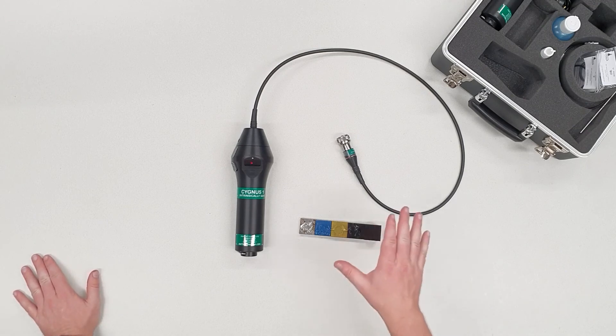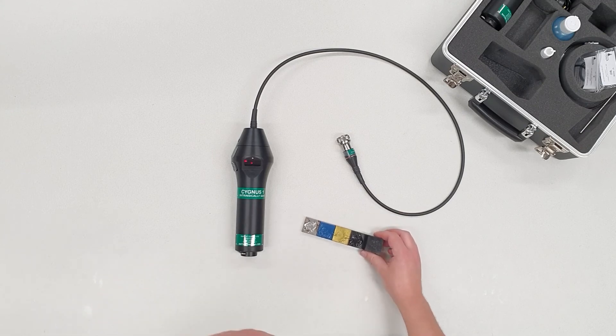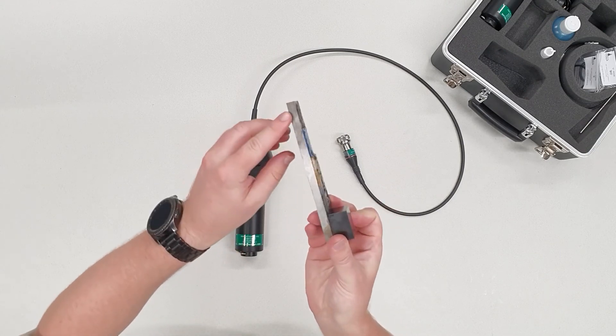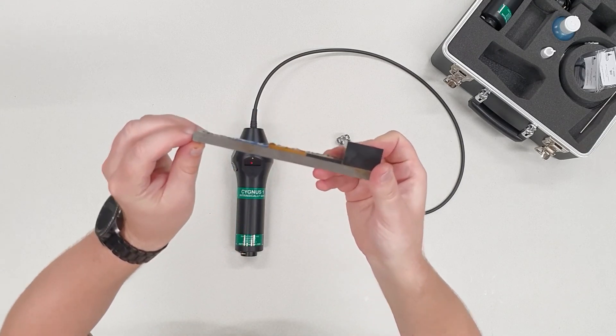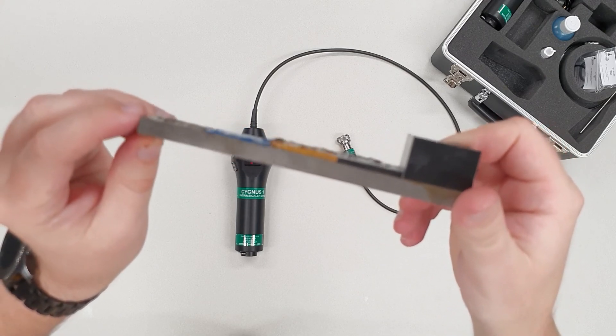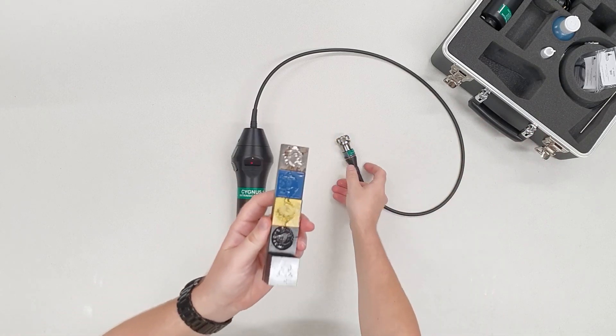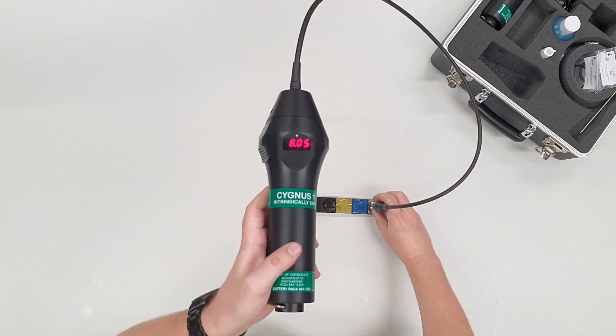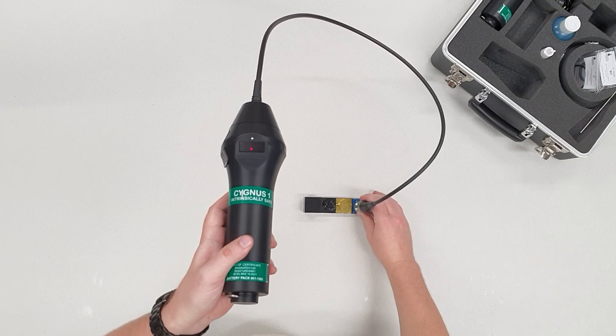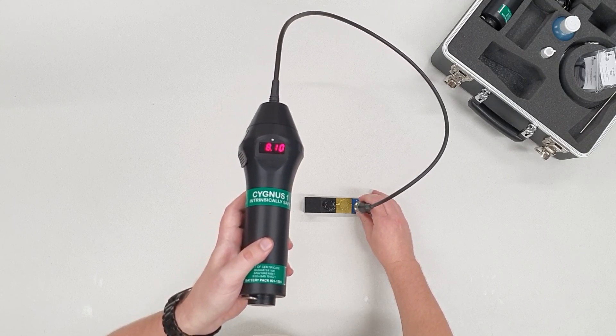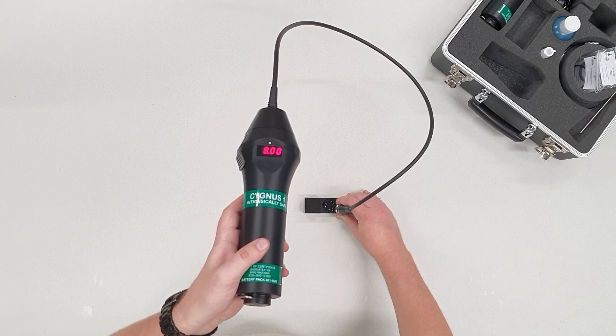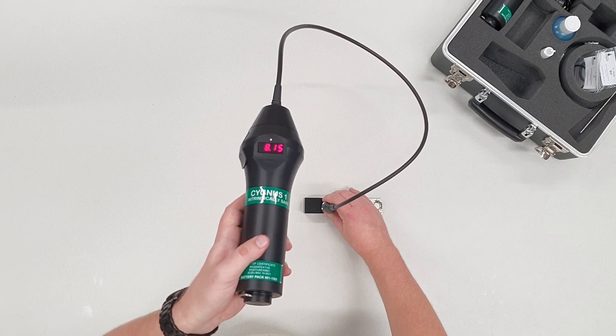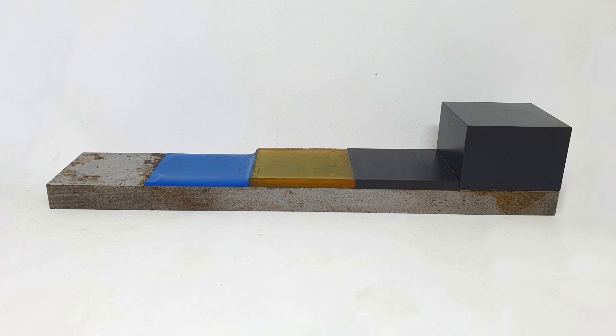One of the best features of thickness gauges is a function known as through-coating measurement, which means it will ignore coatings like paint and just measure the material underneath. Here I have a sample of an 8.1 mm steel block with various coatings of various thicknesses on it. On bare steel, we have a reading of 8.05. On the first coating, still reads 8.05. Second coating, 8.05. And the last coating, 8.1. Just a little bit of variance, but as you can see they are quite a bit thicker than 0.1 of a mil. It has ignored the coating completely.